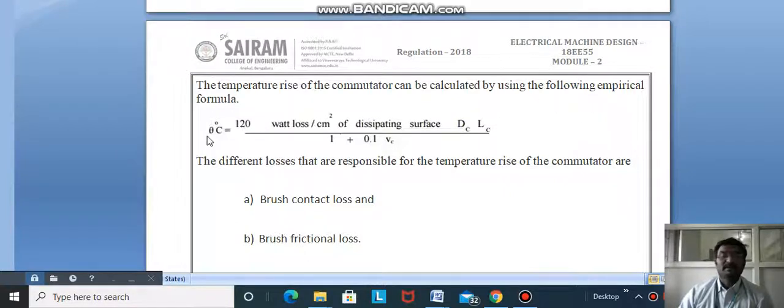The temperature rise of the commutator can be calculated using the following empirical formula: degrees Celsius equals 120 times watt loss per cm² of dissipating surface Dc Lc divided by 1 plus 0.1 Vc.